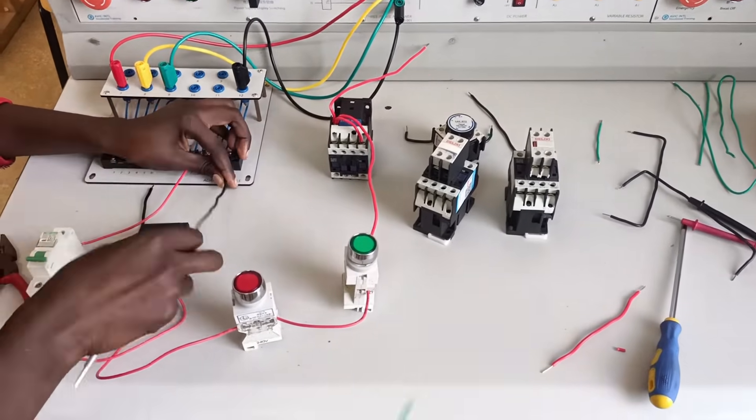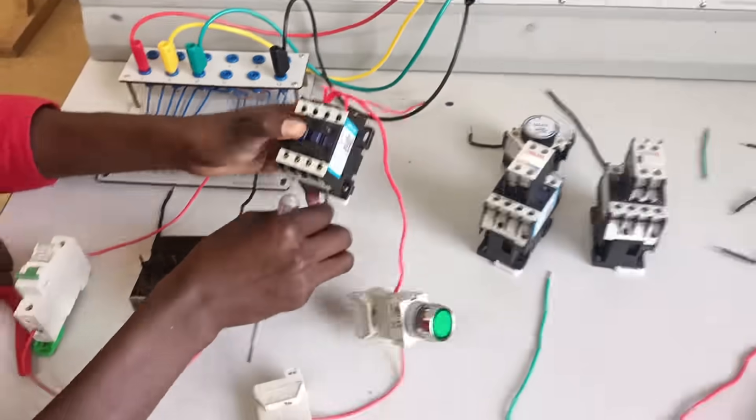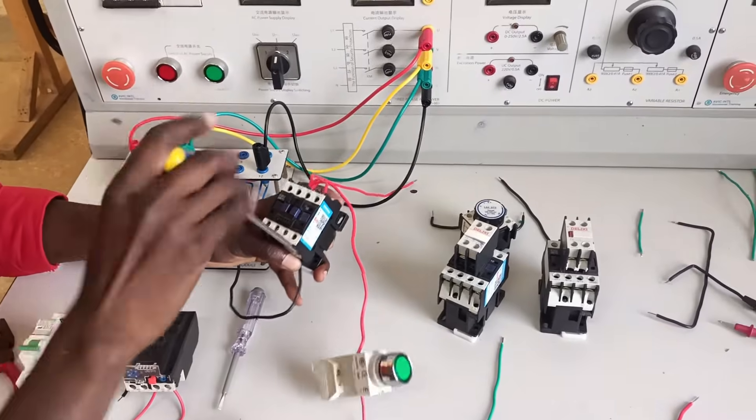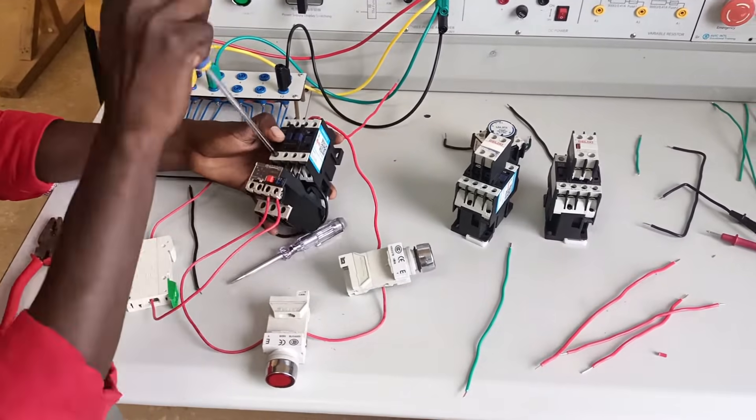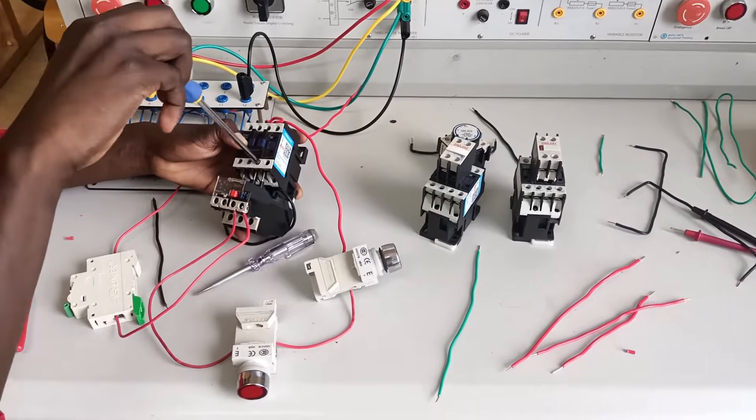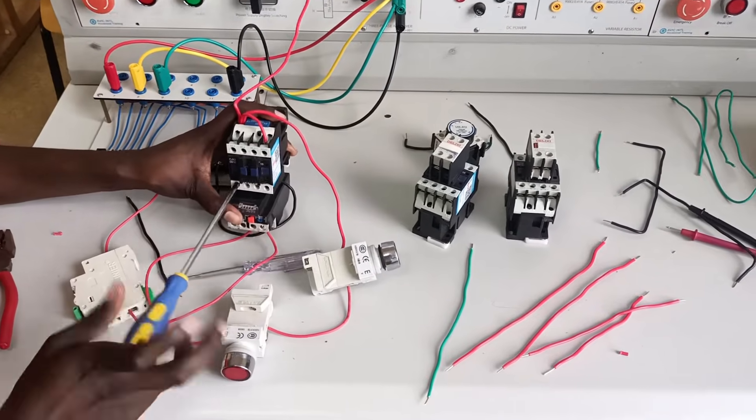Now let's terminate the A2, that's the neutral, to the A2 of the main contactor. In that case the energizing coils are complete. My thermal overload relay interlocks with the contactor, that's why it's so easy to do. But for your case if you need cables to do that, kindly do so.